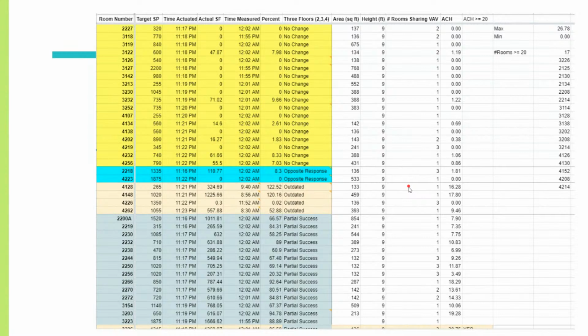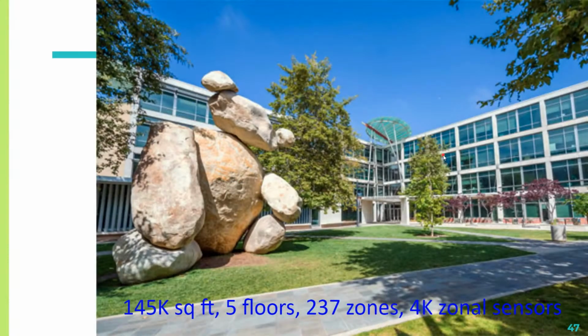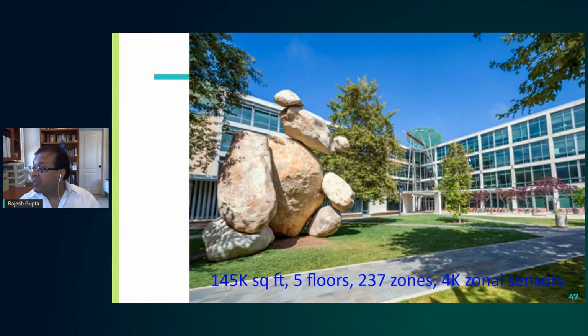Now, in those days, it was just an issue of saving energy. But in the days of COVID, you can imagine what problem this can lead to. You think you're getting fresh air, but your airflow valve is stuck, and therefore you're actually getting much more stale air, and that can lead to a super spreading event, especially in a meeting room or a conference room. So we are already fixing those in this particular building currently. You can imagine the 237 zones, 250 rooms, and so on.